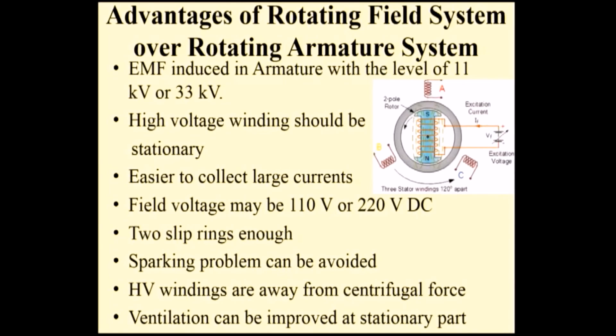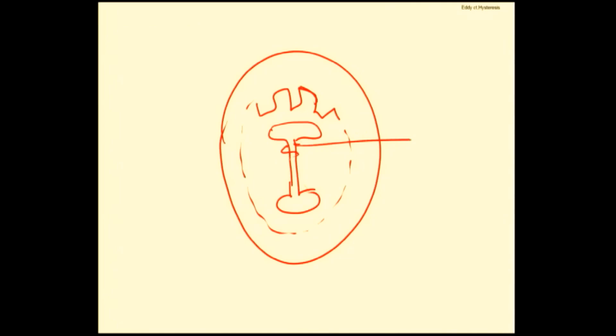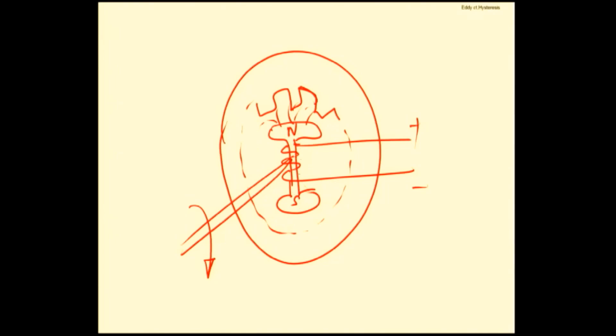Since the large-voltage winding is stationary, ventilation can also be easily provided. So the rotating field stationary armature is clearly the best choice. In this arrangement, the armature's inner periphery is made up of a number of slots; inside is the field system, which receives DC supply. The north and south poles are created, and this field is rotated by mechanical input. While rotating, the flux lines close from N to S, cutting the armature conductors in the slots and inducing an alternating EMF that can be directly tapped.